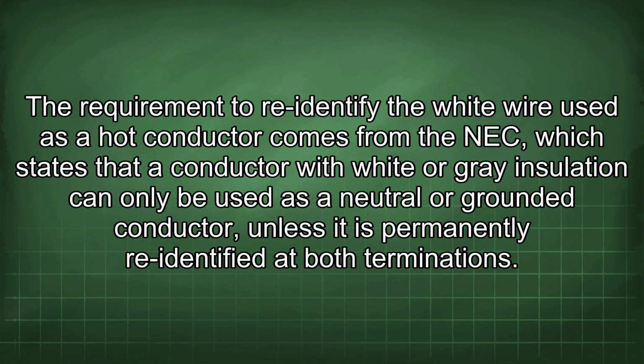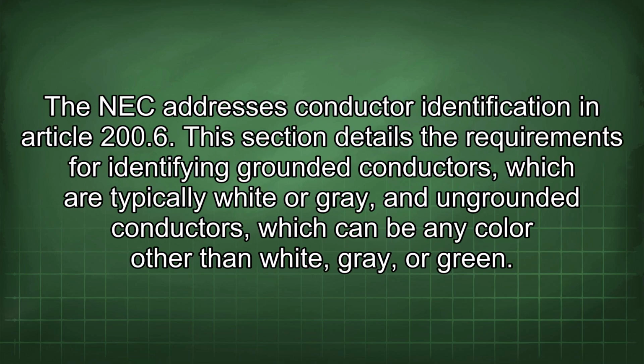The requirement to re-identify the white wire used as a hot conductor comes from the NEC, which states that a conductor with white or grey insulation can only be used as a neutral or grounded conductor unless it is permanently re-identified at both terminations. The NEC addresses conductor identification in Article 200.6. This section details the requirements for identifying grounded conductors, which are typically white or grey, and ungrounded conductors, which can be any color other than white, grey, or green.